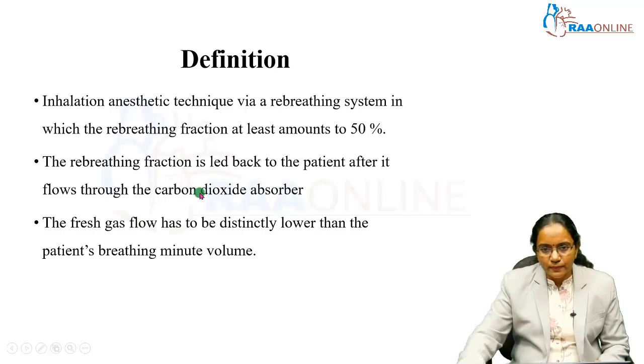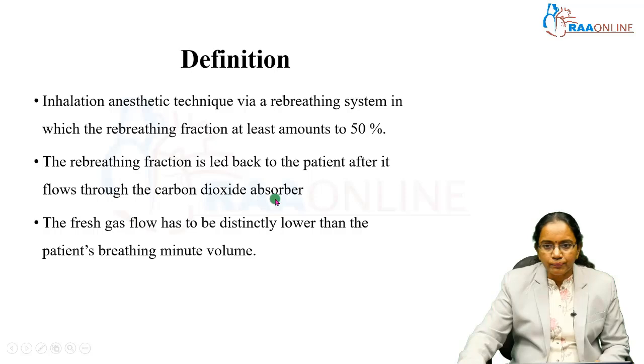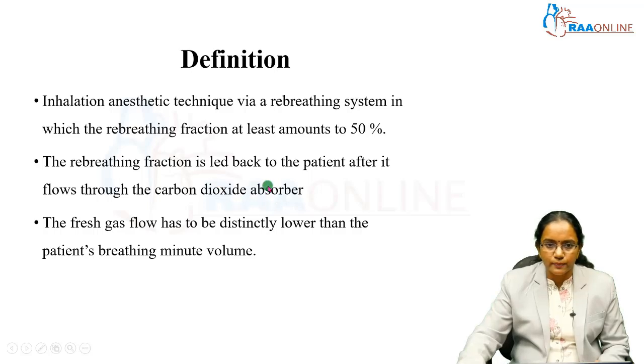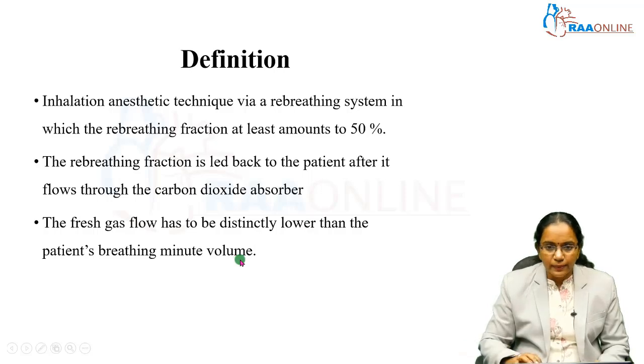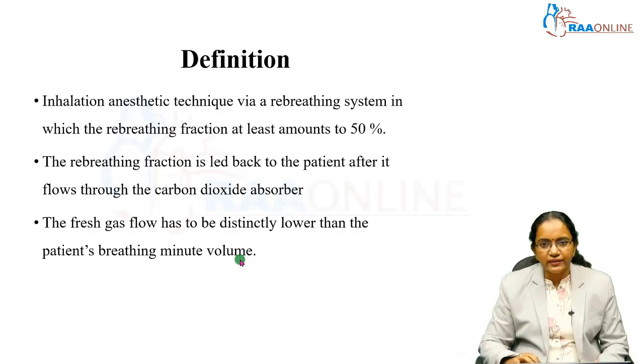The carbon dioxide absorber absorbs all the carbon dioxide which is exhaled by the patient, and then the re-breathed air is led back to the patient after it passes through the carbon dioxide absorber. The fresh gas flow has to be distinctly lower than the patient's breathing minute volume — this defines low flow anesthesia.